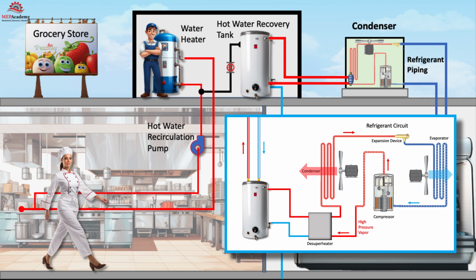By utilizing the waste heat from the air conditioning or refrigeration system, the desuperheater reduces the workload on the service water heater's primary heating source. This can result in significant energy savings and increased overall system efficiency, as the water heater doesn't have to work as hard to reach the desired temperature.